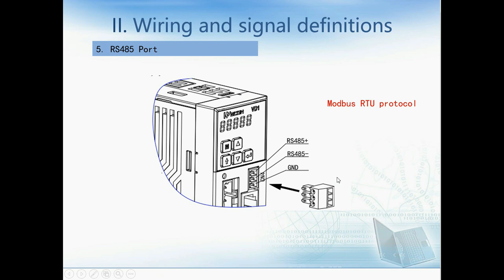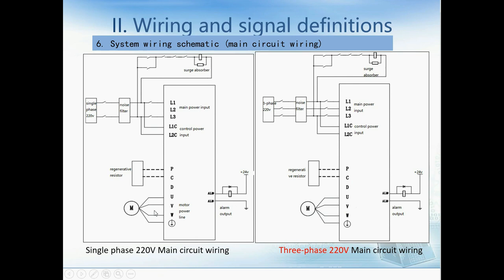This is the RS-485 port for Modbus RTU protocol. Here is the main circuit wiring. The WeconServo drive can support single-phase 220V or three-phase 220V power input. So far it does not support three-phase 380V, so we need to pay attention to this.